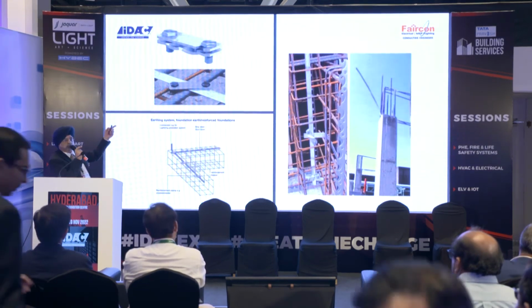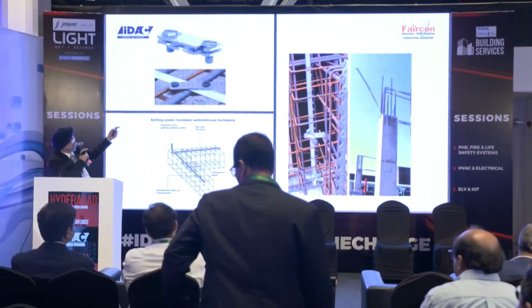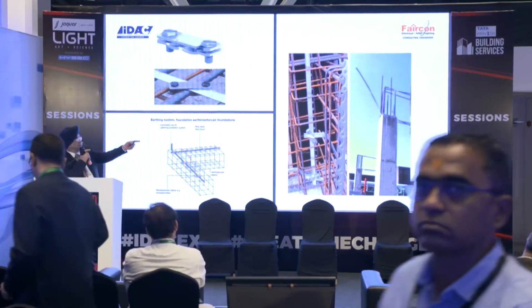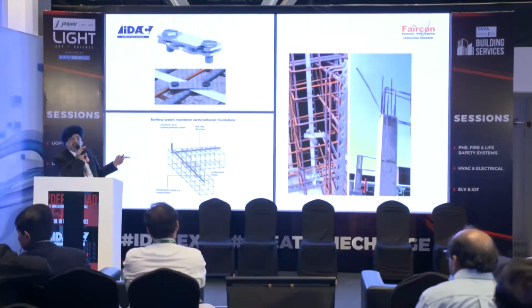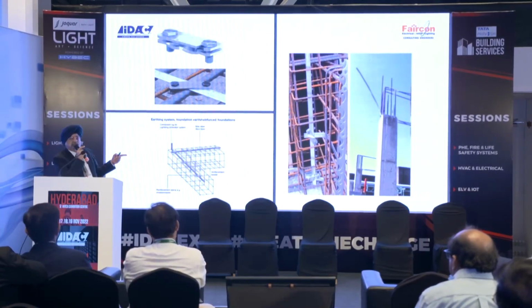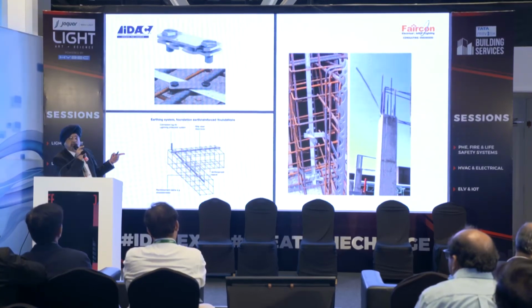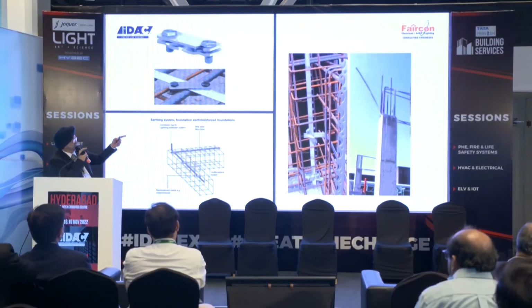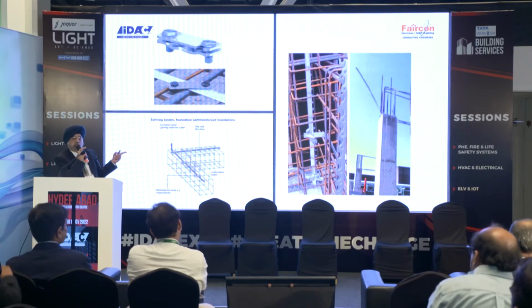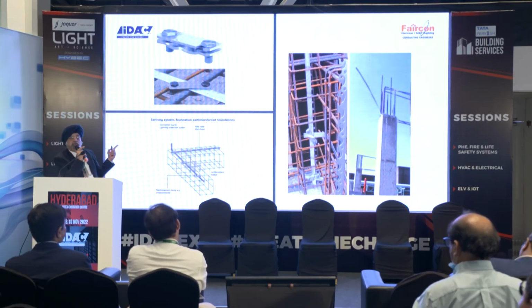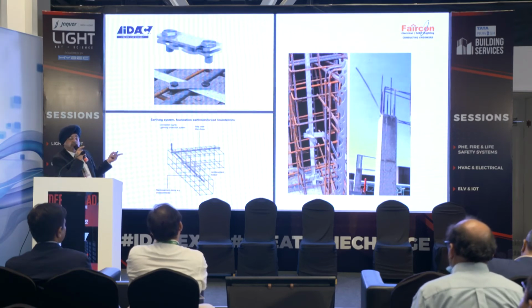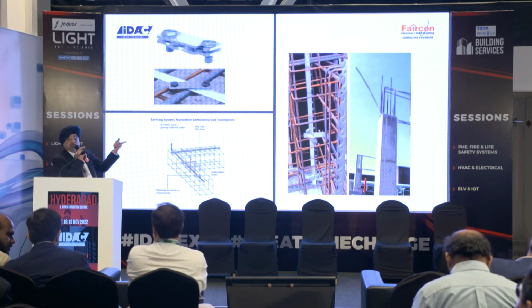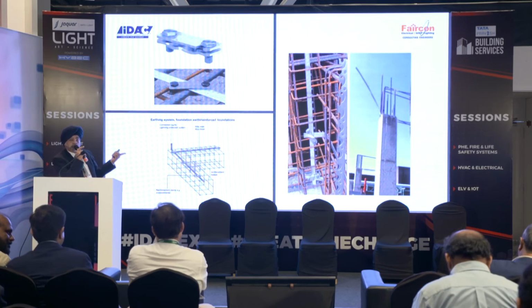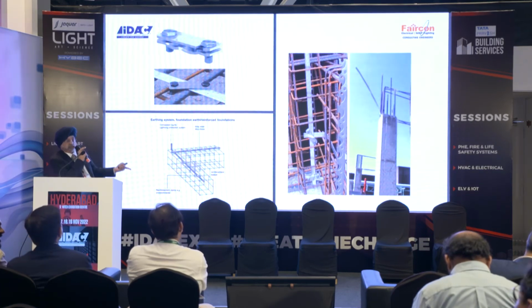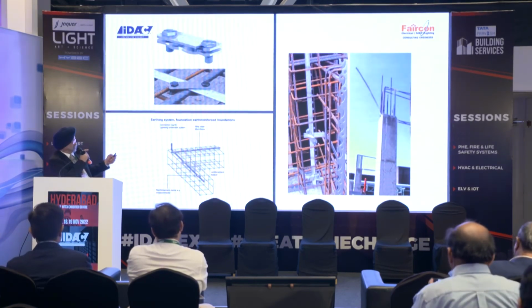These are the components of the lightning arrestor. Please note, this is very unique: your RCC angular structure can be used as a down conductor. You don't have to lay a down conductor separately. While casting, if you have bonding done on an ongoing basis, you can use it for bringing it down to ground.